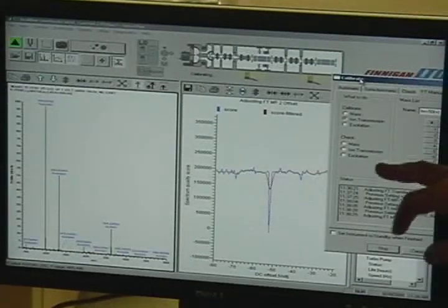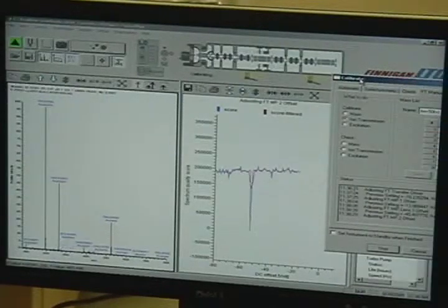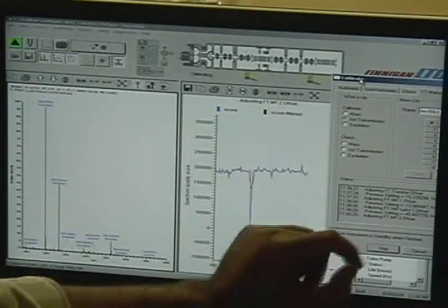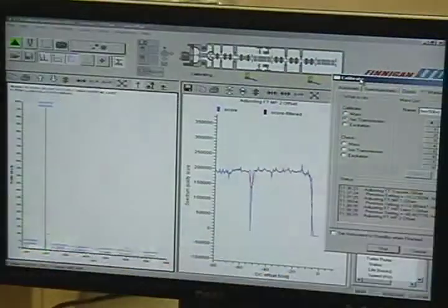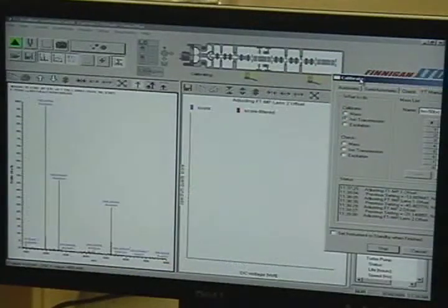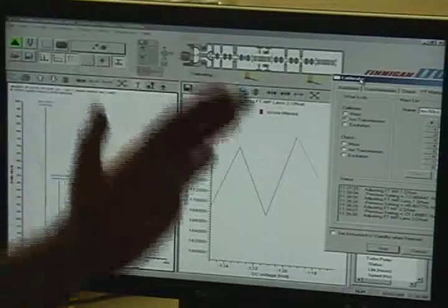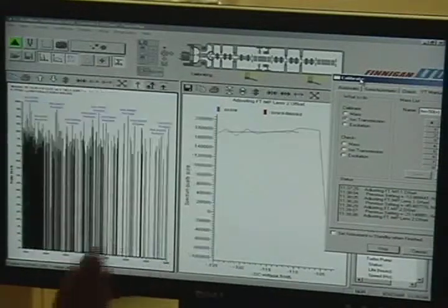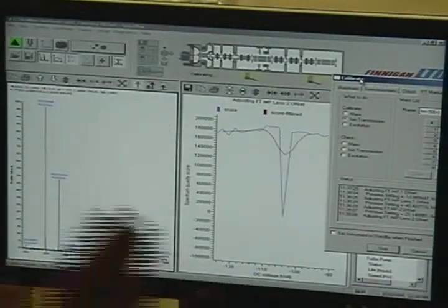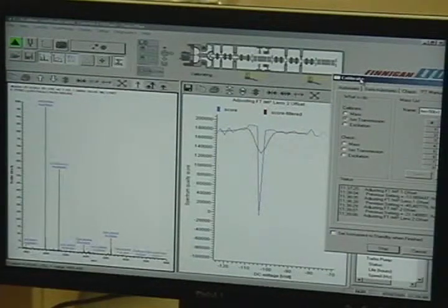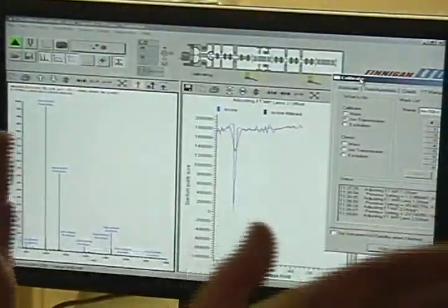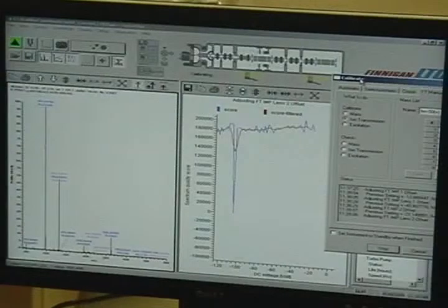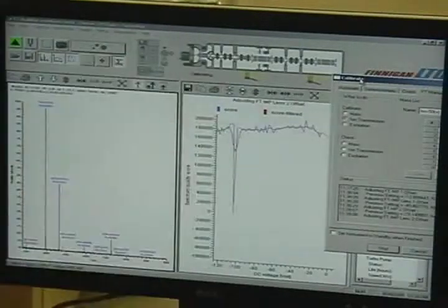Doesn't it automatically do mass calibration after you do ion transmission? But I always hit stop. You just hit stop, or you just recalibrate. You have to do the mass separately. When you do the mass calibration, you should just do the normal list, because that covers the whole range. You can use different mixtures for transmission and excite. It doesn't matter what you mix it with. Mass calibration is what needs to cover the whole range you're going to scan, and then the transmission is mass heavy where you want it to transmit the best.